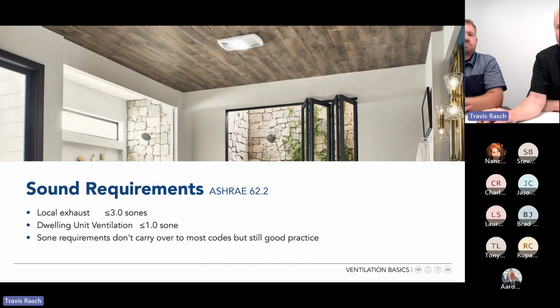Real quickly, a sidebar to touch on sound requirements. 62.2 says you should stay under 3 sones for local exhaust and under 1 sone for dwelling unit ventilation. These don't usually make their way into the actual I codes, but it is still good practice. Whatever type of device you're using, if the homeowner is going to turn it off because they find it objectionably loud, now they have no ventilation. So quiet operation really is a key consideration.